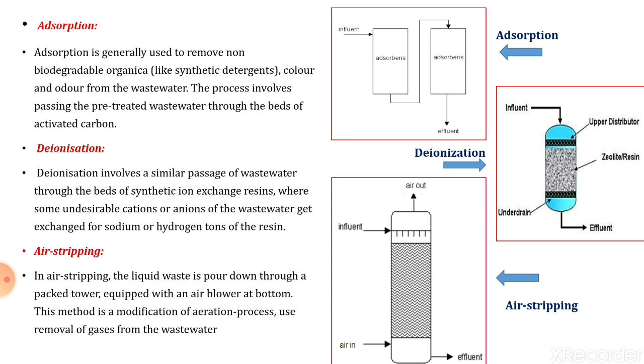Adsorption is generally used to remove non-biodegradable organic material, colour, and odour from wastewater. The process involves passing the pretreated wastewater through a bed of activated carbon. The colour, odour, and non-biodegradable organic material adhere on the surface of the activated carbon, causing separation of such matter from the influent. The clear effluent is then taken out, and the adsorbent is regularly and routinely replaced.